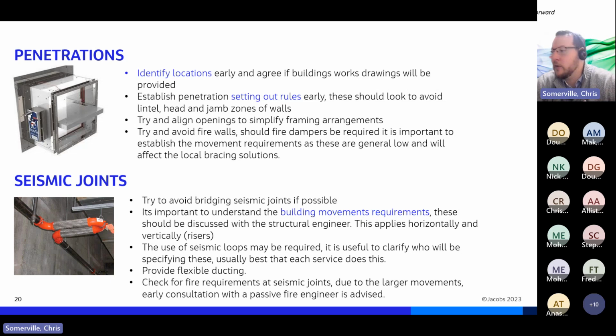If possible, avoid firewalls. They can be expensive to go through, and you might need fire dampers, which can be quite limiting on movement. So occasionally we may have to put restraints close up to the wall to limit the movement of the service passing through a fire damper to meet that requirement. Understanding that early on is good.